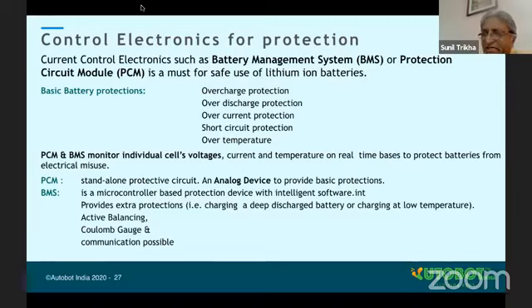We are not monitoring the overall battery, we are monitoring each and every cell. Not even a single cell should exceed its fully charged condition, and not even a single cell should go deep into the deep discharge condition. So we monitor the voltage of each and every cell in the battery continuously, in real time, and set parameters: the upper voltage limit for overcharging, and the voltage limit for deep discharging.